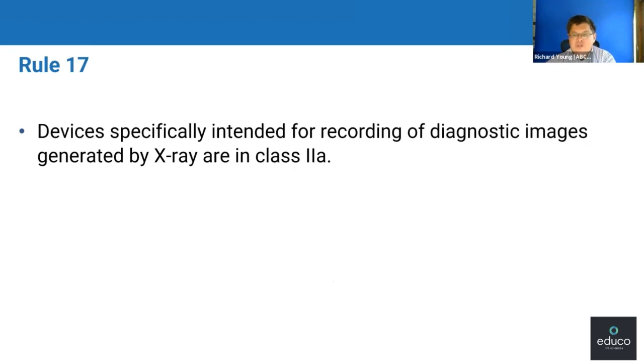and images, so that's DICOM systems that capture images and handle them around. Those are class 2A medical devices. They get a higher risk classification than you might otherwise think, because it's really important the right X-ray, unaltered, goes to the right patient file and is reviewed correctly by the doctor. It's one of the most important things about diagnostic imaging. We need to make sure the right image goes with the right patient.